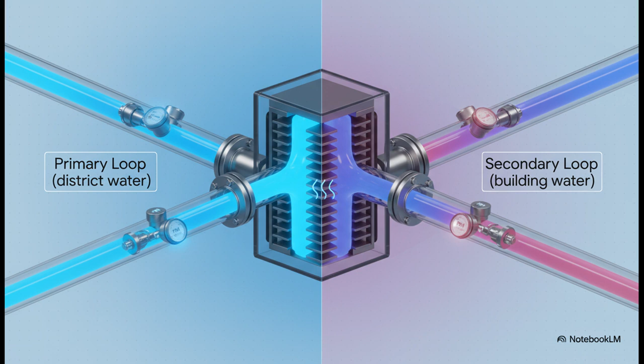On the left, you've got the primary loop, that's the city's water. On the right, you've got the secondary loop, that's the building's water. Inside that heat exchanger, they get incredibly close, passing heat energy between them, but, and this is vital, they never ever mix. This separation is everything. It means a problem in one building, like a leak or some contamination, can't crash the entire city's grid.